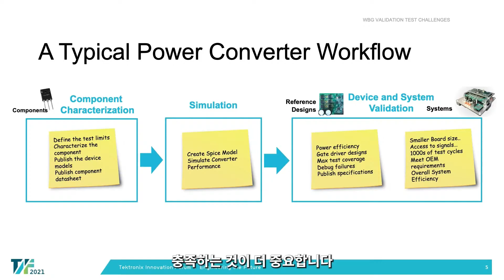Finally, we have the validation block. Here, the engineers are working on some early reference designs and end systems. This is where components that were characterized at the first stage get integrated. Some of the common focus areas include gate driver reference designs, designing for highest efficiency, debugging failure, and publishing the reference design documentation. And for system engineers, it's more around trying to reduce the board size, gaining access to the test signals, and meeting the OEM's requirements.